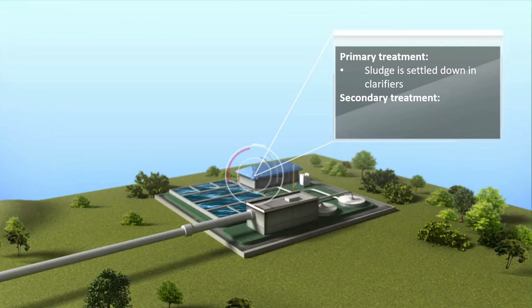Non-settlable solids such as dissolved sugars are still left in the wastewater after primary treatment. Secondary treatment uses microorganisms and oxygen to convert dissolved solids into biological masses which can be removed later. Depending on the local permits, the nutrients after this stage might not be a concern for release into natural waterways or groundwater.